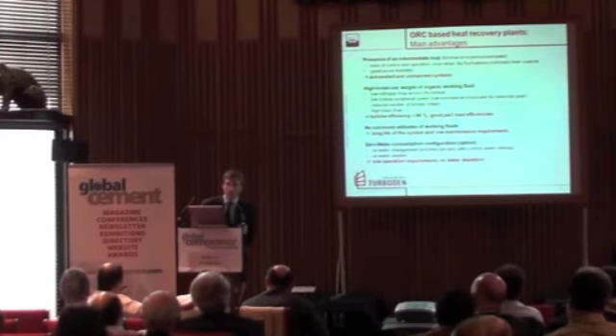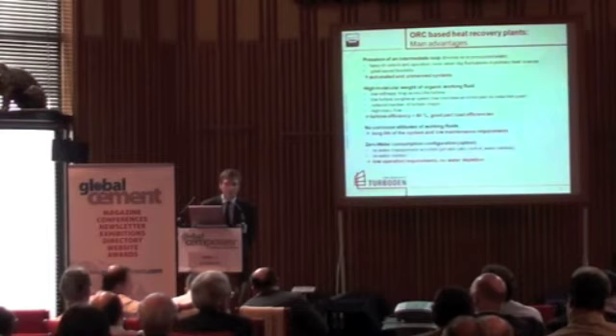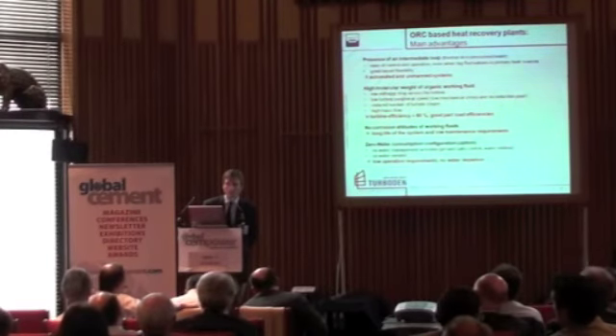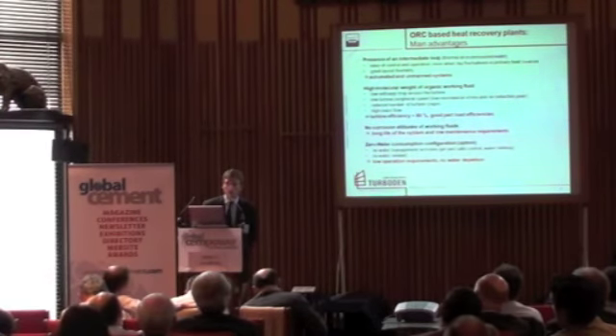So the first question, capital cost. ORC has an additional loop instead of direct exchange of working fluid with the heat source. We have a thermal oil, which brings automation of the system as an advantage. Clearly, it brings some additional capex as a disadvantage. So this is the cost for an automated system. The other one was running cost. Typically we are achieving 1% of the capex. From what I know about steam solutions, and we have experts here, they are typically greater, at least twice. Specifically in relation to the operation, one person in total is enough to run our ORC-based plant.